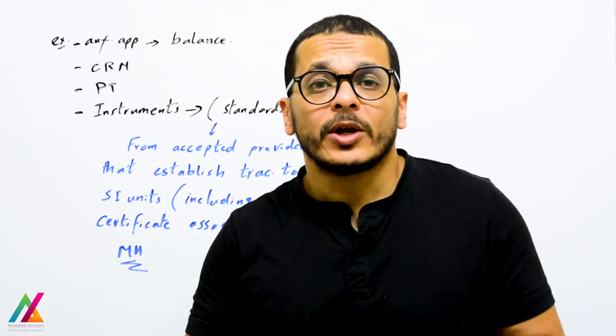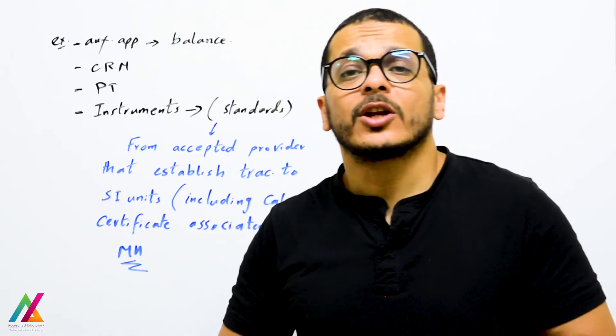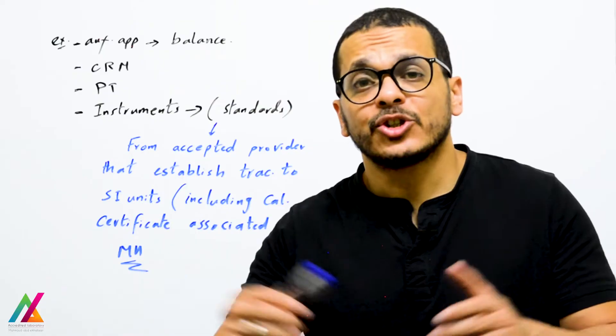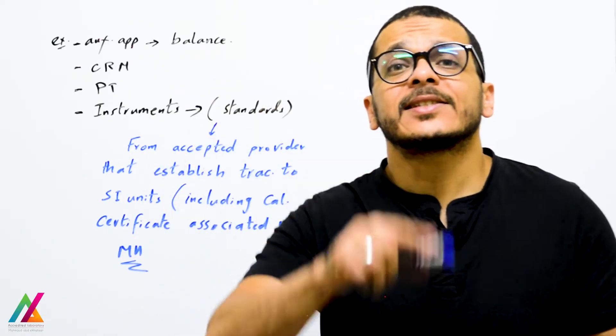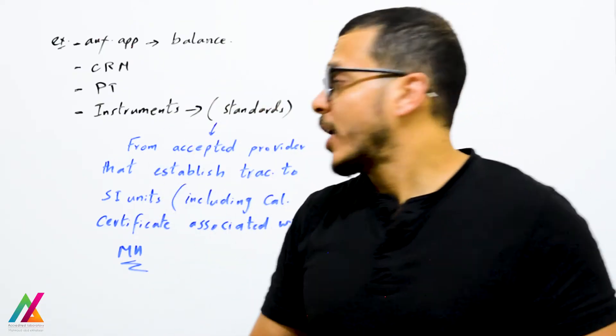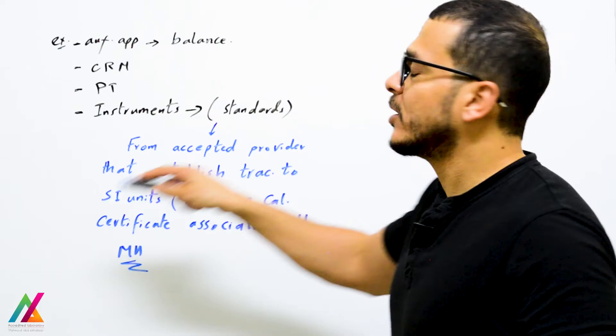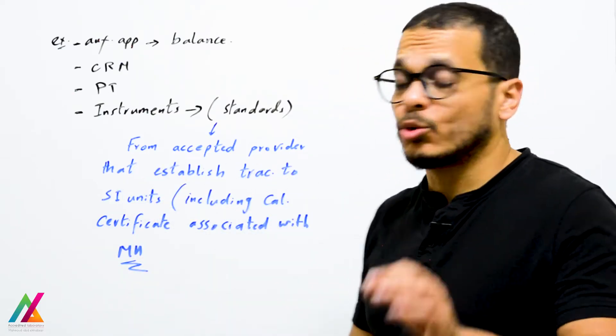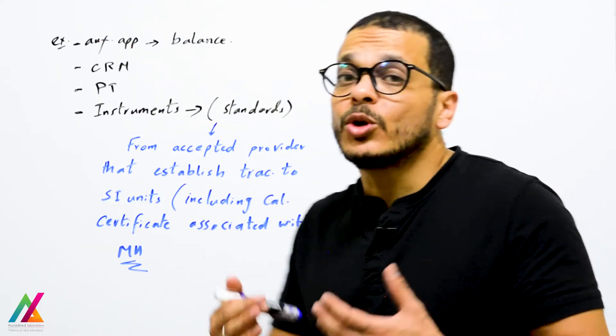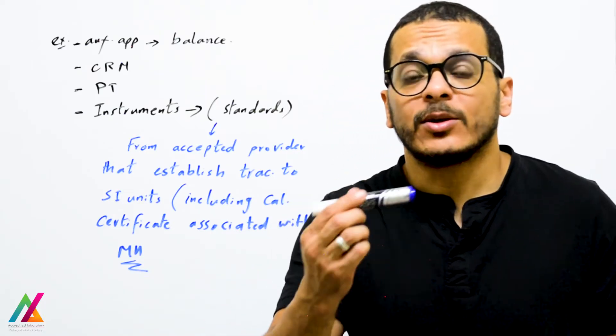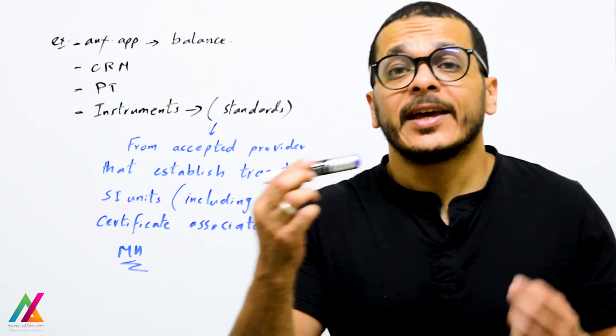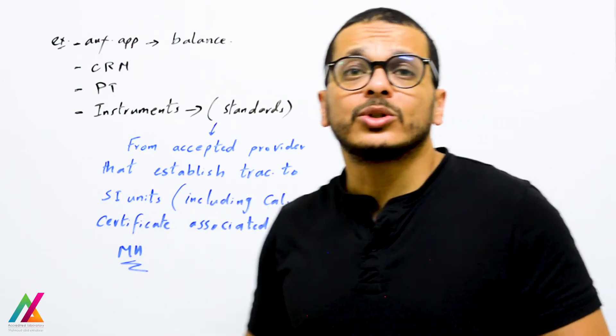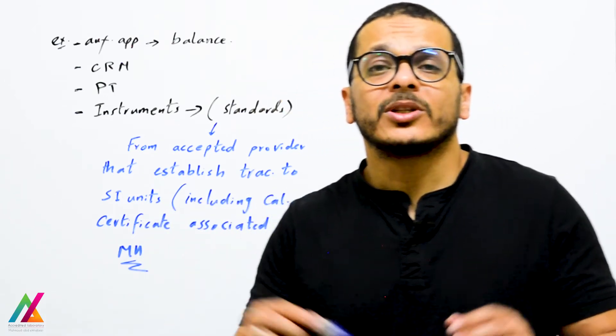For measuring instruments inside the lab, each instrument shall be calibrated by measurement standards, and those standards shall be from an accepted provider that establishes traceability to SI units. They will provide a calibration certificate, and these certificates include the measurement uncertainty.